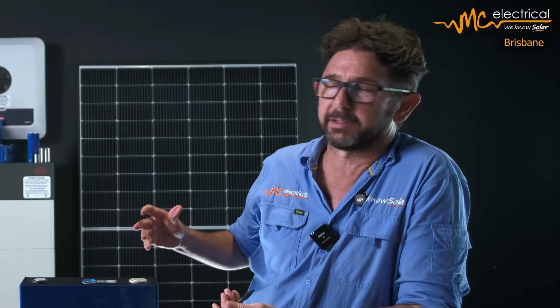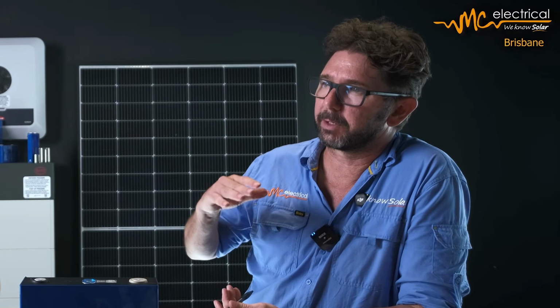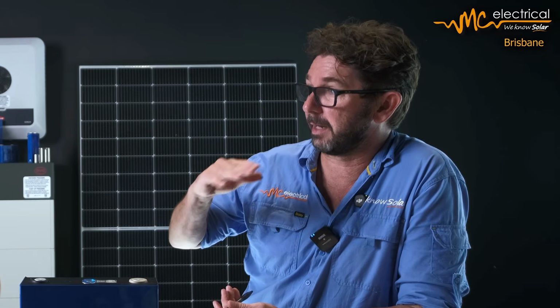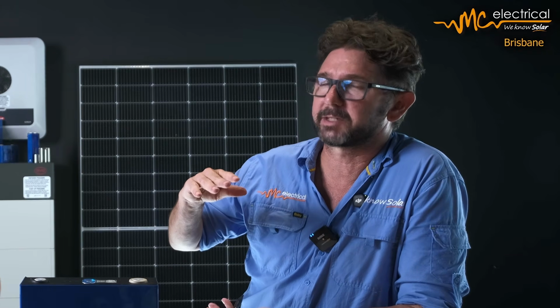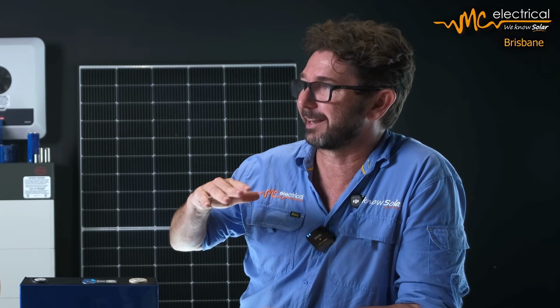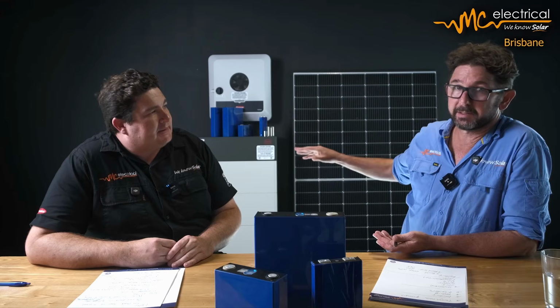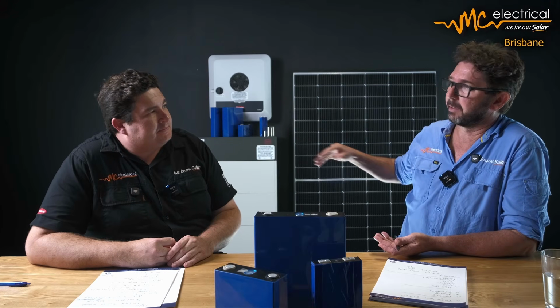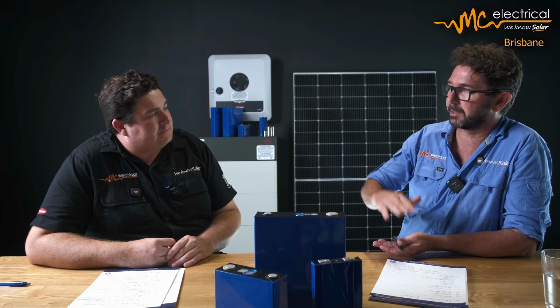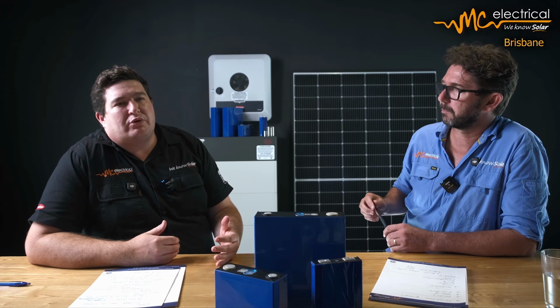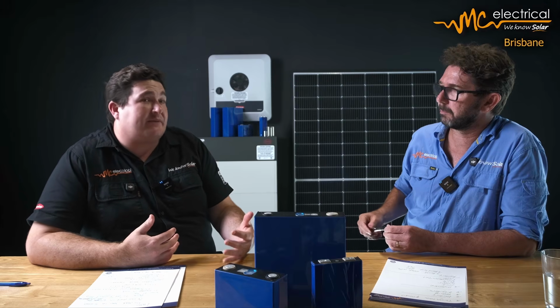One thing I learned about it, which I think is a good trick, is that if you're not totally oversizing your battery, they've got a reserve setting at 10% of the battery, so you never discharge more than 90% unless you're in a blackout. Fronius has 7% but we can adjust that; with Fox we can adjust it down to 0. I think that's potentially not a bad idea - I don't think it's a bad idea either, but I'd caution dropping it all the way to 0. You want the battery to last a long time, even if it is fairly cost effective.